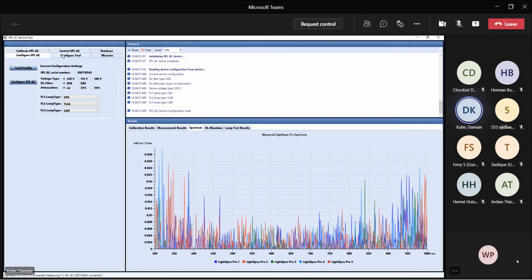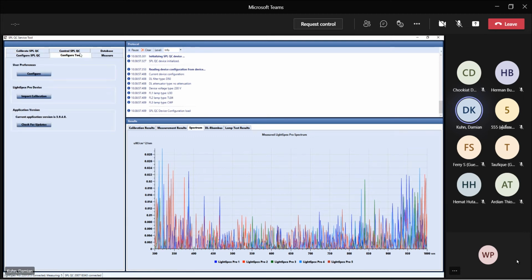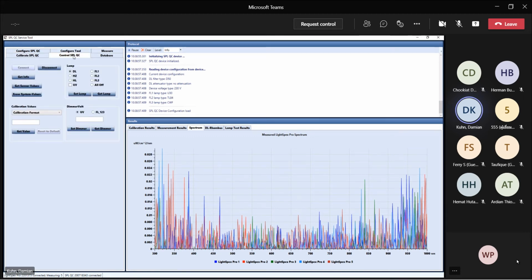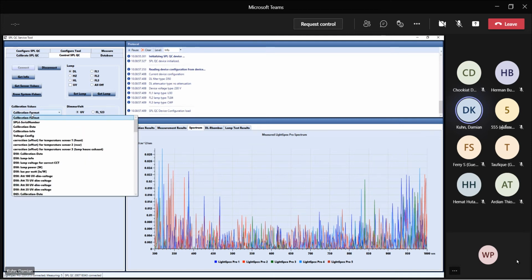And then I'm coming to the last one I would like to talk about, and that is really if you're going to control SPLQC. This is where, in case you are in that situation where the instrument always turns off one of the halogen light sources during the calibration sequence with an overcurrent message, you could go to that specific light source. So let's say it would happen on this instrument on the daylight light source. So you would actually go to daylight lamp voltage for correct CCT.